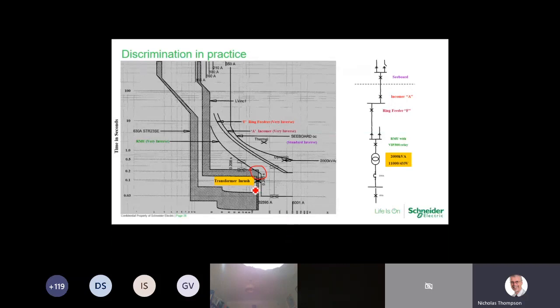When you take into account transformers, because of the very nature of a transformer, we've got to take into account where our transformer inrush peak is going to be, and they put the transformer inrush on the HV side below the ring main unit curve. If that transformer inrush point was higher than the settings on the VIP 300, then we've got the potential for nuisance tripping. Every time we switch the transformer on from cold, we would likely see a nuisance trip, and then somebody having to go out and reset it every time. So that's how it all works in practice.